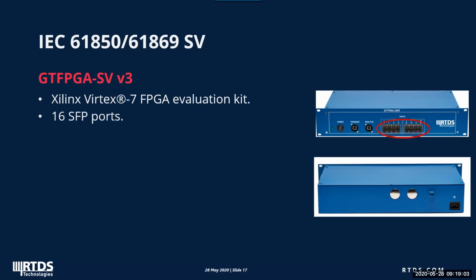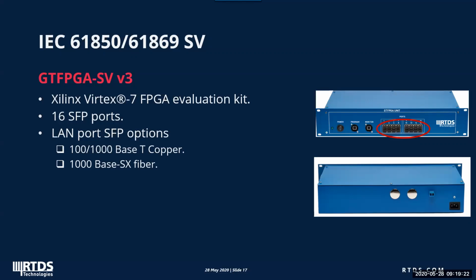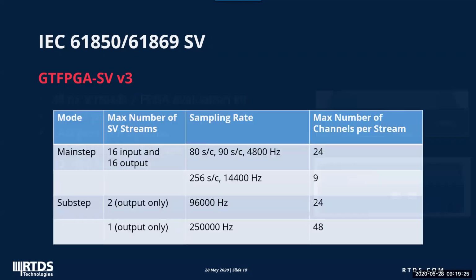As shown in the picture, the first difference we can see between the GTNet X2 and the GT FPGA unit is that there are 16 Ethernet ports available on the front panel of the GT FPGA unit. Whereas for GTNet X2, there are only 2 ports, one for each independent running GTNet module. So no surprise, due to the extra ports, the GT FPGA SV can publish and subscribe up to 16 streams simultaneously. Remember that a GTNet X2 SV module works in one mode only at a given time.